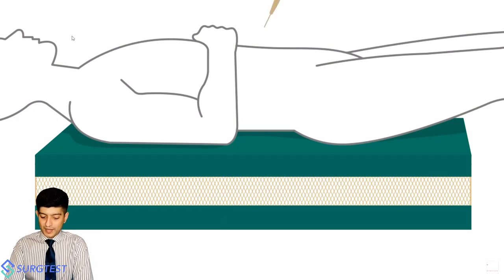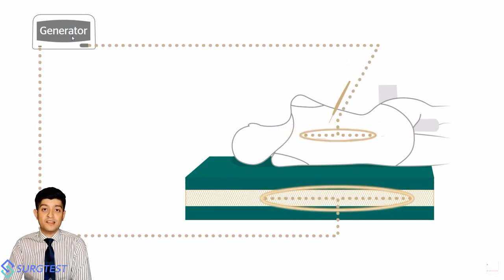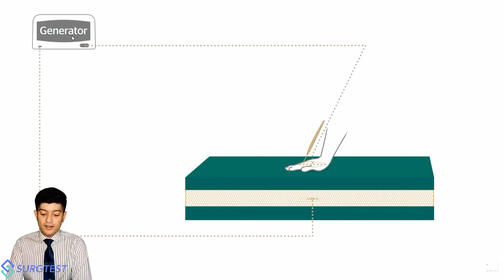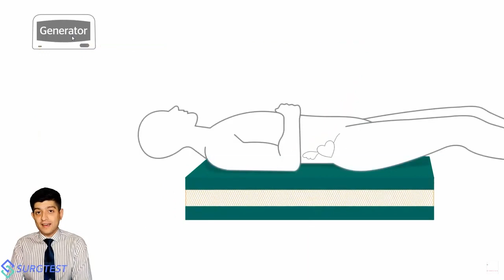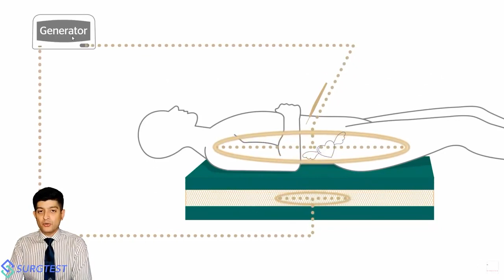Instead, the patient and this pad behave like a capacitor, where they just store charge. And the alternating nature of the voltage means that the charge is stored and then reversed extremely rapidly. It is this shift in the amount of charge present on the patient side that eventually produces the oscillation of ions, the heat, and this conversion of energy. Now, remember, if the amount of contact between these two areas reduces, automatically the capacitance to hold ions reduces. So there is a lesser likelihood that great energy will be delivered even when the area is narrowed. So the problems of partial application of a dispersive pad are not applicable to a capacitive electrode.